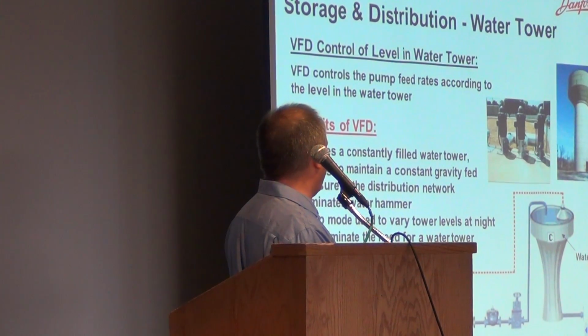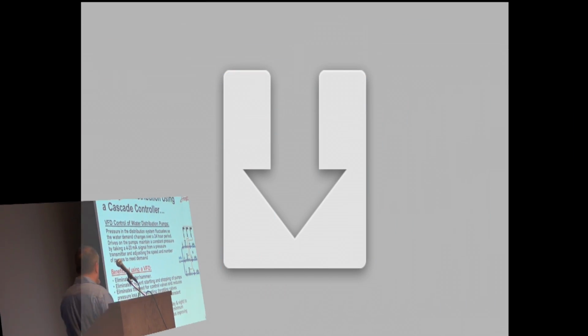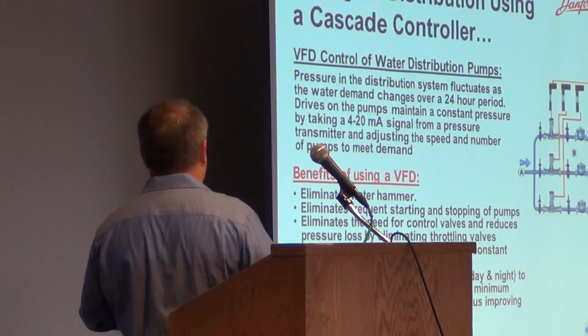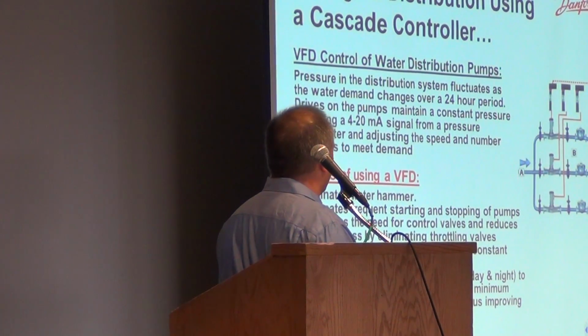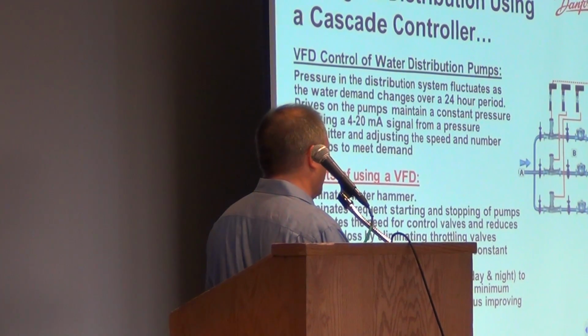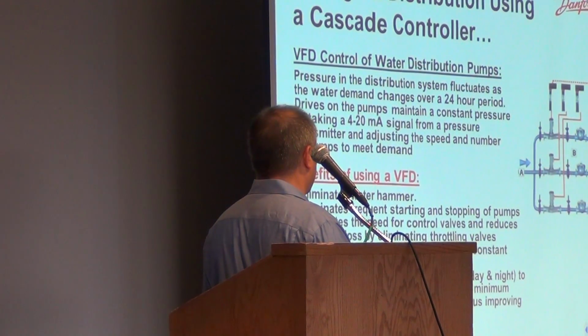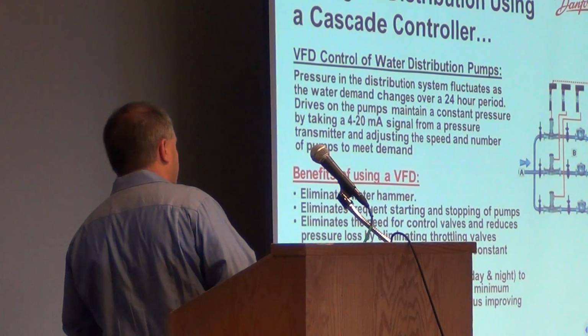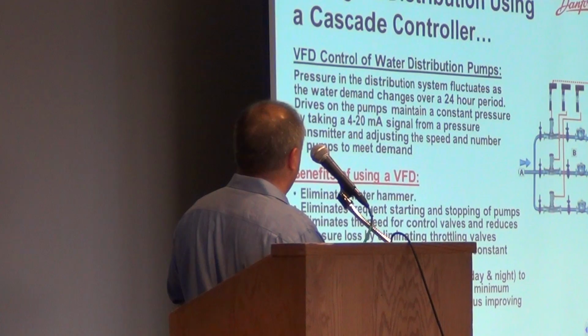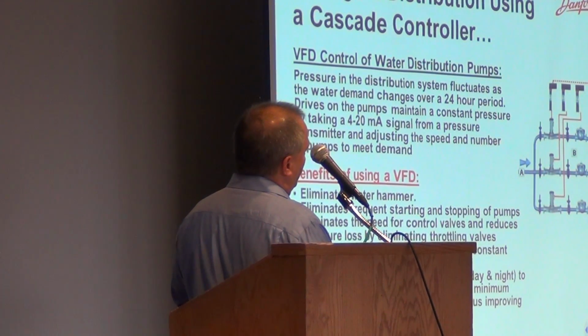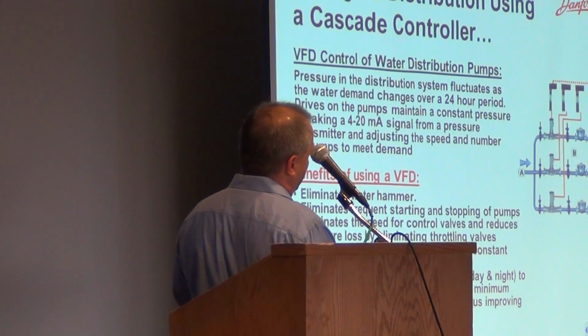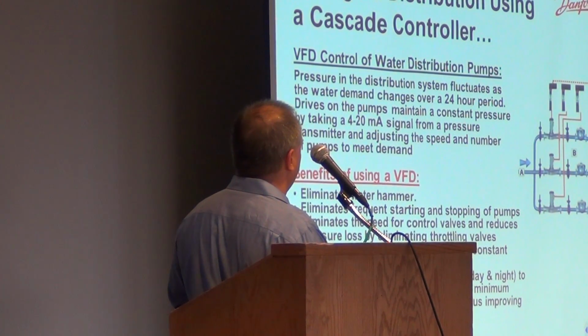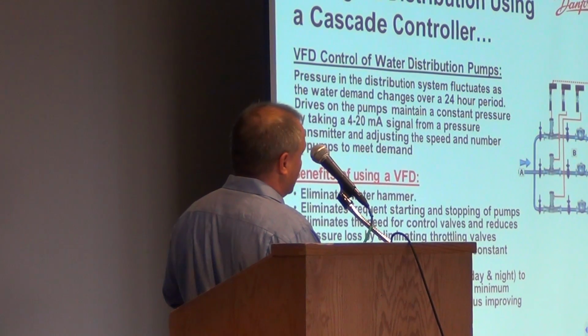There's many advantages to putting the drive on your well. The biggest benefit is that it eliminates water hammer. Stops your frequent starts and stops on your pumps. It reduces your maintenance costs on your control valves, on your discharge valves, on your pump. Maintains multiple pressure points, and it reduces water leakage because you don't have the high pressure like on a high service pump that you have to valve back. Everything between that drive and between that pump and that valve is under higher pressure than what's on the back side of it.